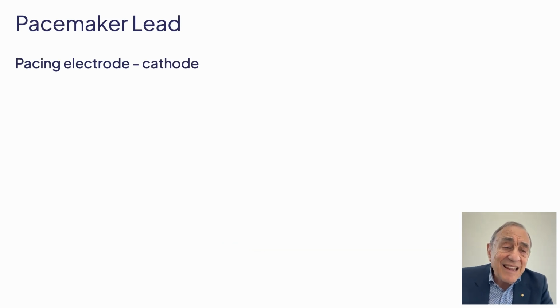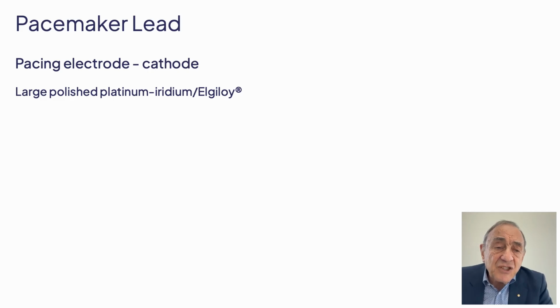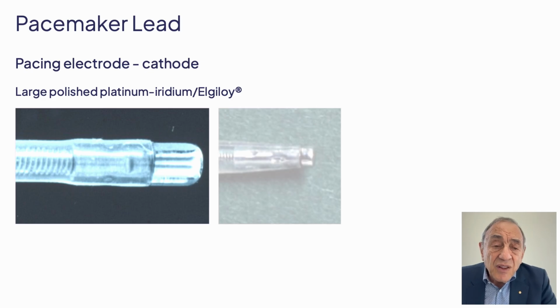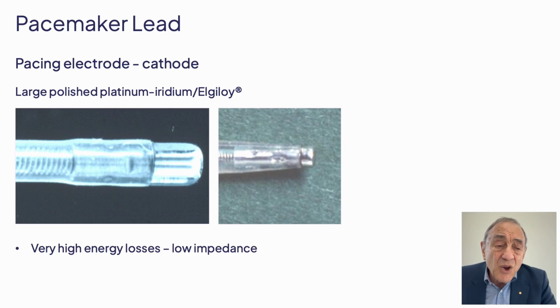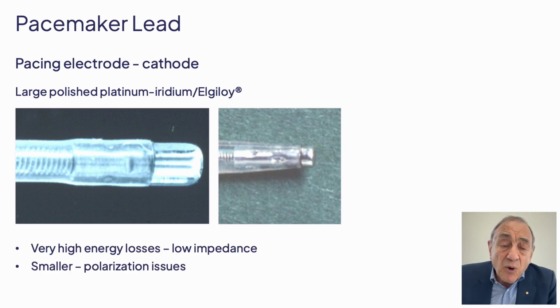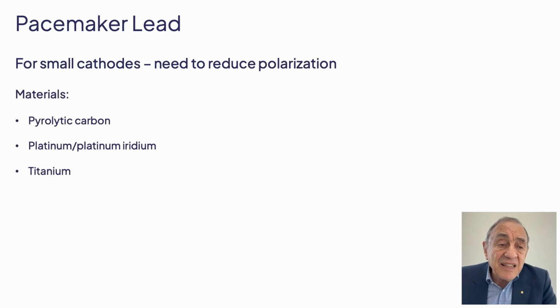Let us now look at the cathode. Initial ones were large polished platinum iridium, as can be seen here. These were then reduced in size, and as a result we had high polarization, which is a disadvantage with pacing. We needed, therefore, to reduce the cathode size but also to have a respectable polarization. This can be done with materials such as pyrolytic carbon, platinum iridium, or titanium.